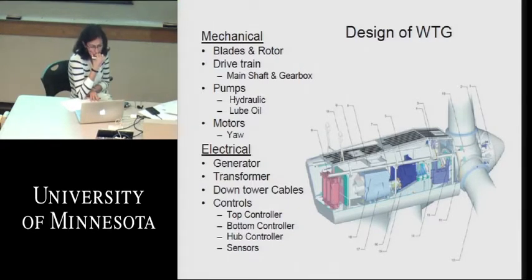Since we generally bring the power out of each individual wind turbine underground, as you see in our designs here, we use standard conventional distribution equipment like any utility would use to bring power to your house. In your neighborhood, you'll have a small pad mount transformer in a residential community, and that's doing the same thing. It's taking the power and stepping it down from this medium voltage at say 25 kV or 12 kV, and bringing it down to a useful voltage you would use in your house at 220 to 240.